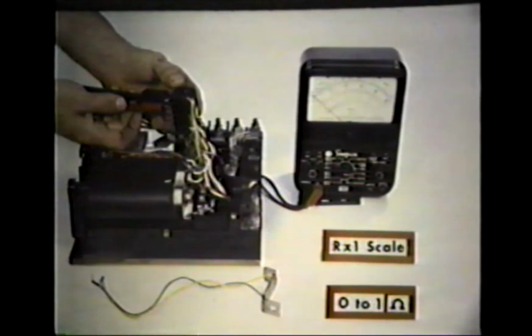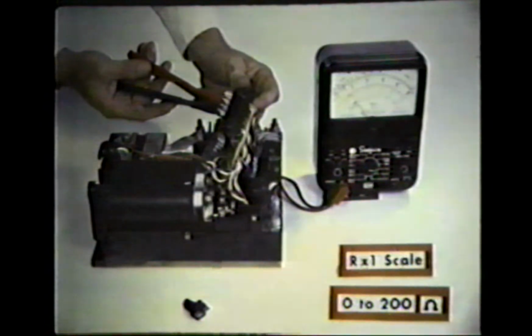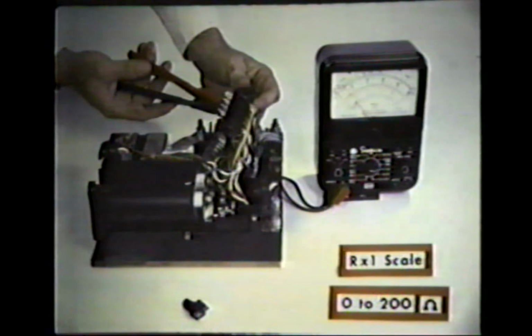Test the sensor from the yellow to green wire at the card plug terminals 13 and 14. Meter should show 0 ohms on the R times 1 scale. Also, check the thermal protector at the card plug where the orange and brown wires connect to terminals 11 and 12. Ohm readings should be 0 to 200 at room temperature.